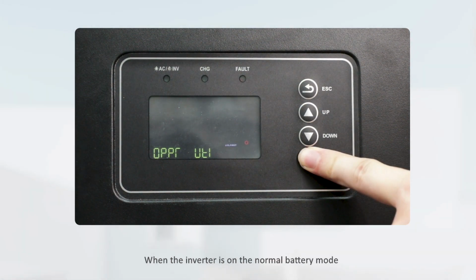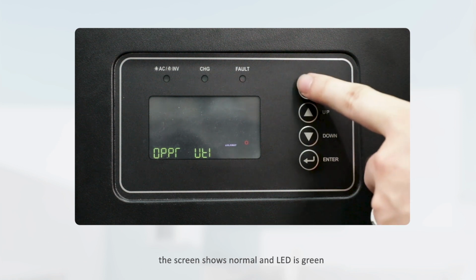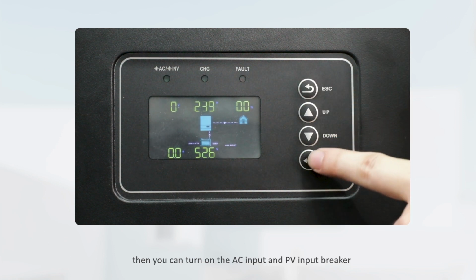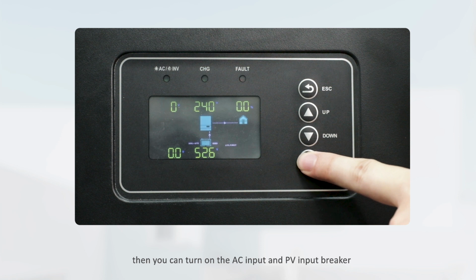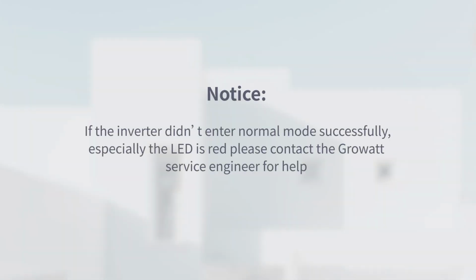When the inverter is in normal battery mode, the screen shows normal and the LED is green, then you can turn on the AC input and PV input breakers. Note: if the inverter didn't enter the normal mode successfully, especially if the LED is red, please contact a Growatt service engineer for help.